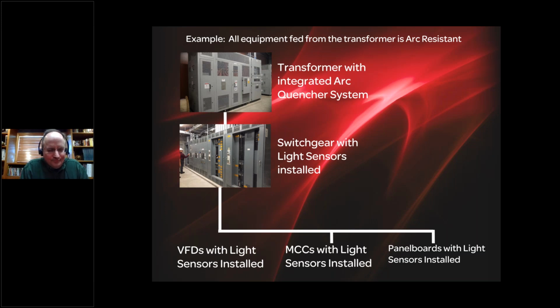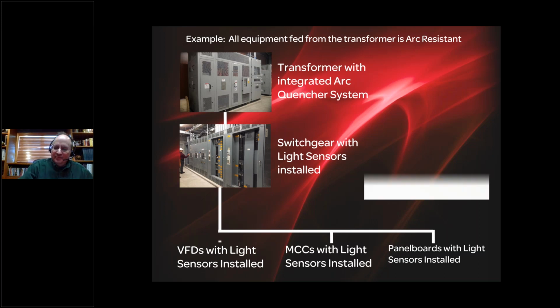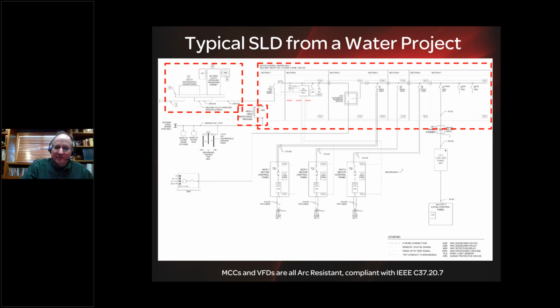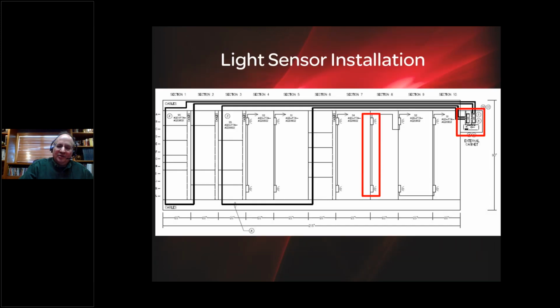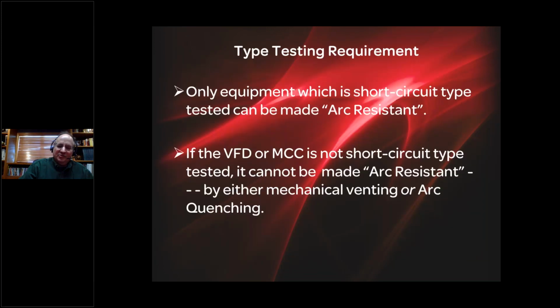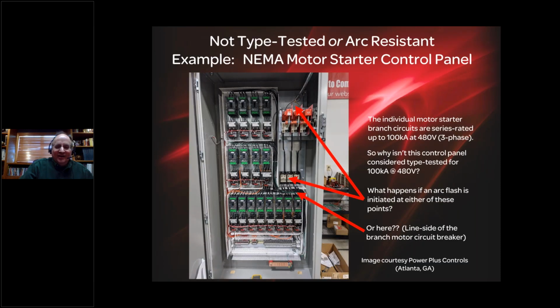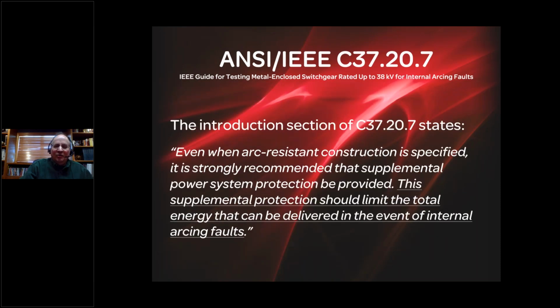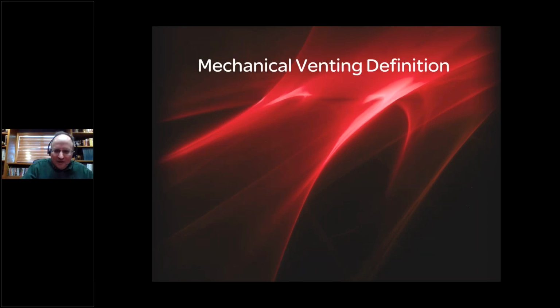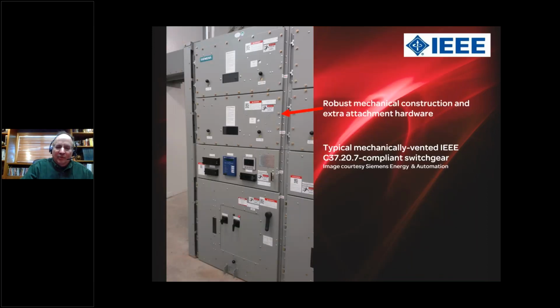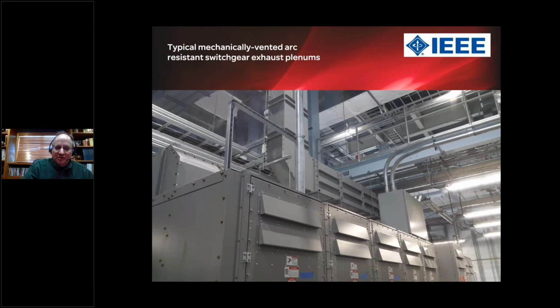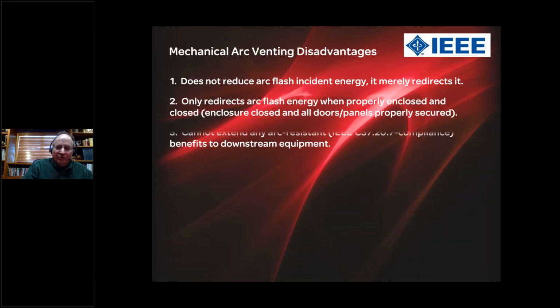Okay. Next question is, you mentioned point light sensors. Don't you have to add CTs? Oh, absolutely. So if CTs are not there, let me go back to where I showed the arc quencher system here. It'll take me a second. The CTs, though, I don't need CTs in the downstream equipment. The CTs are already in the upstream equipment with the arc quencher. I do not need to add CTs in the motor control center or the drive cabinet.